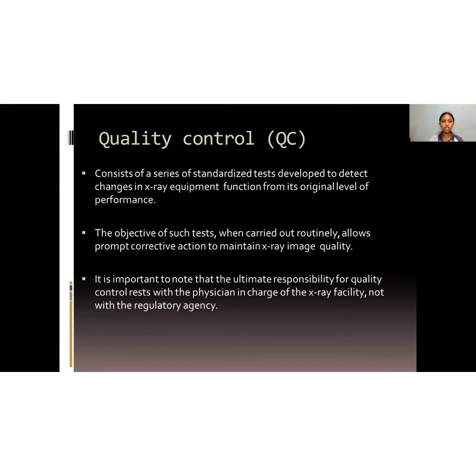Quality control consists of a series of standardized tests developed to detect changes in X-ray equipment function from its original level of performance. The objective of such tests, when carried out routinely, is to allow prompt corrective action to maintain X-ray image quality. It is important to note that the ultimate responsibility for quality control rests with the physician in charge of the X-ray facility, not with a regulatory agency.